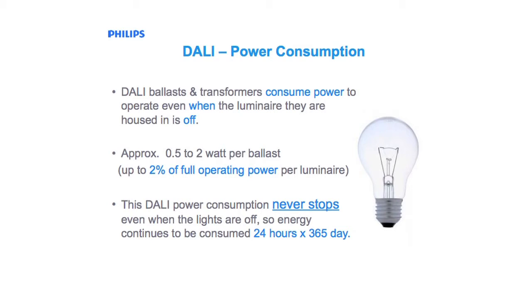DALI ballasts consume power even when the lamp is turned off. This is what is referred to as the standby current consumption. When the lighting control system has instructed the ballast to turn its lamp off, it will be in standby mode, waiting for a signal to turn the lamp back on. The DALI ballasts will continue to consume this standby power even when the lights are off. This consumption never stops, 24 hours a day, 365 days a year.